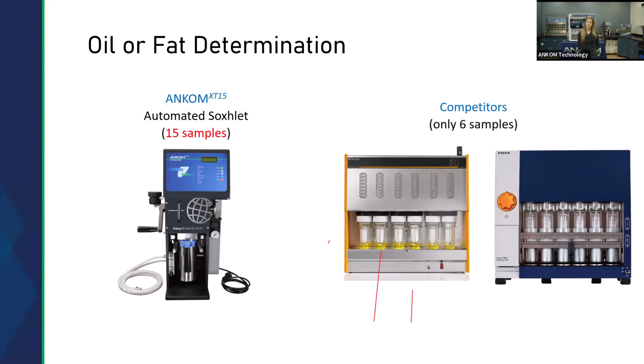This instrument is also enabled by filter bag technology, which eliminates that glassware. You can do 1 to 3 gram sample sizes, and you can analyze a fat content of 0 to 100%, so there really isn't a limitation on this. Everything is done automatically, as I mentioned, up to 15 samples per run. It's all computer controlled and done in a closed system, so it's under pressure and elevated temperatures, which greatly accelerates the time it takes to extract your sample.